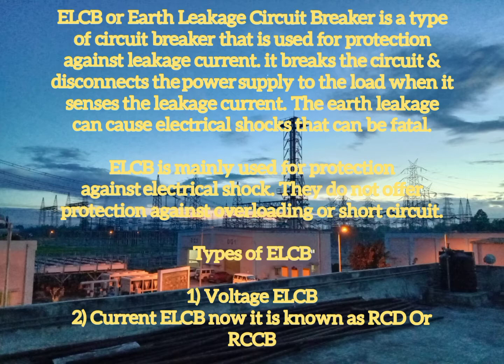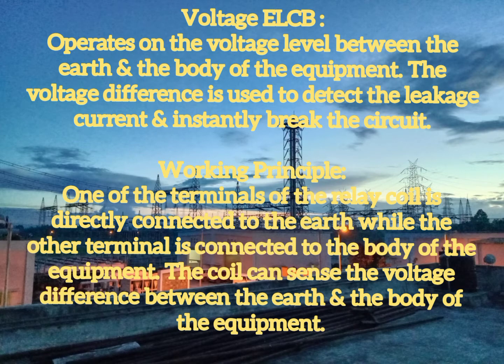It is further classified into two types. One is voltage type and another one is current type. The current type is also known as the RCCB type, which means the RCCB is the current type ELCB. Nowadays we are calling it an RCCB. Next, coming up to voltage ELCBs. It operates on the voltage level between the earth and the body of your equipment. The voltage difference is used to detect the leakage current and instantly breaks the circuit.